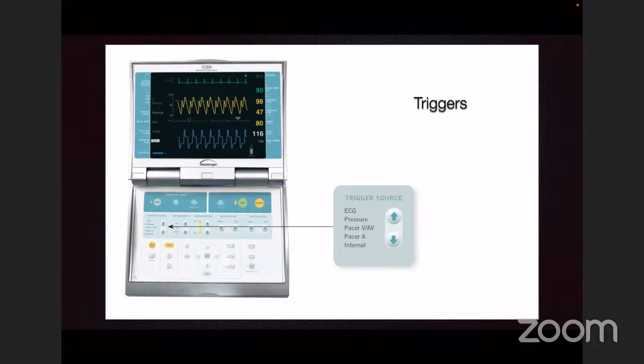Or when the patient is on CPB, at that time also you can use an internal mode to deliver pulsation. Usually on CPB, it is a non-pulsatile flow. If you want to maintain a pulsatile flow, you can use this internal mode and start pulsating the balloon when the patient is on CPB as well. So this is a little about the triggers.